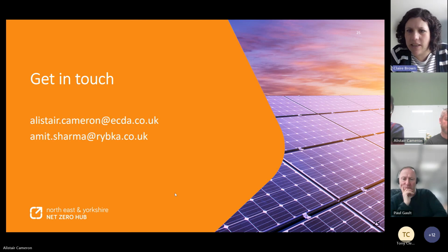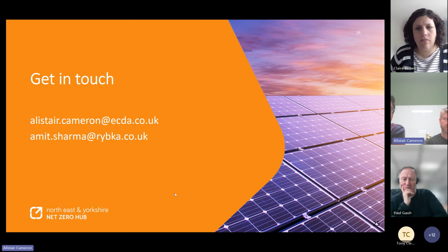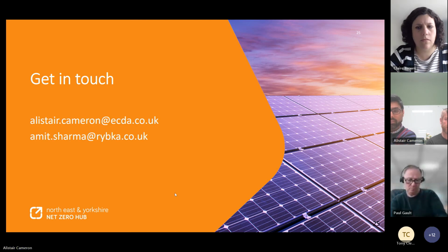Brilliant, thank you. Steffi has asked, is there a way to internally transfer the heat from the overheated side to the cold side? So the heat transfer that we're proposing is from the cold side to the warm side. So we're taking heat that's not needed by the cooling equipment that's serving the ice rink and transferring that heat to the warm part of the building that always needs heat. So that we felt was the most obvious way of transferring energy between parts of the building. And it makes great sense because you've got an ice rink and you've got a swimming pool all in the same building and all requiring different types of energy per year.